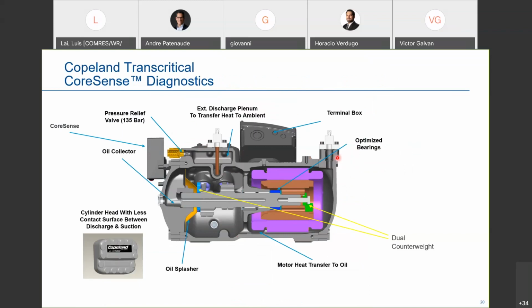UL does not require a suction pressure relief installed. And one of the reasons for it, especially with this compressor, is that if the pressure on the low side of the system gets high enough, it can actually make its way into the valve plate and push the discharge reeds up to allow the pressure to escape up the discharge reed. Because this entire compressor has been burst pressure tested to 10,000 pounds.